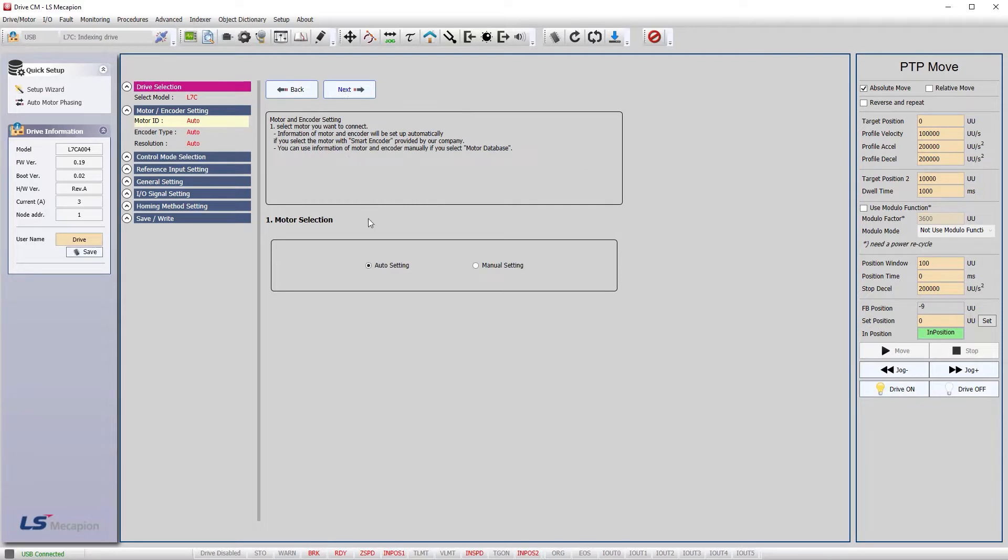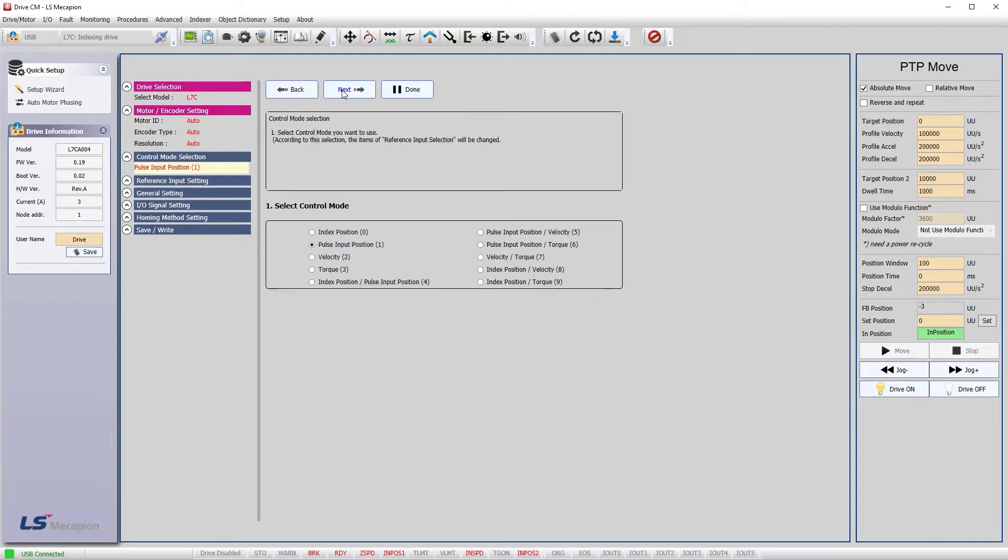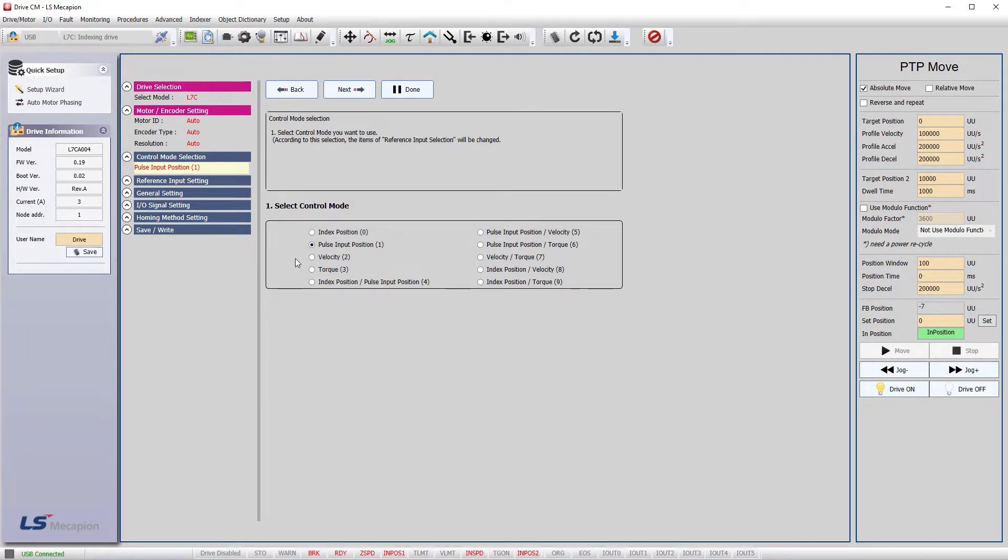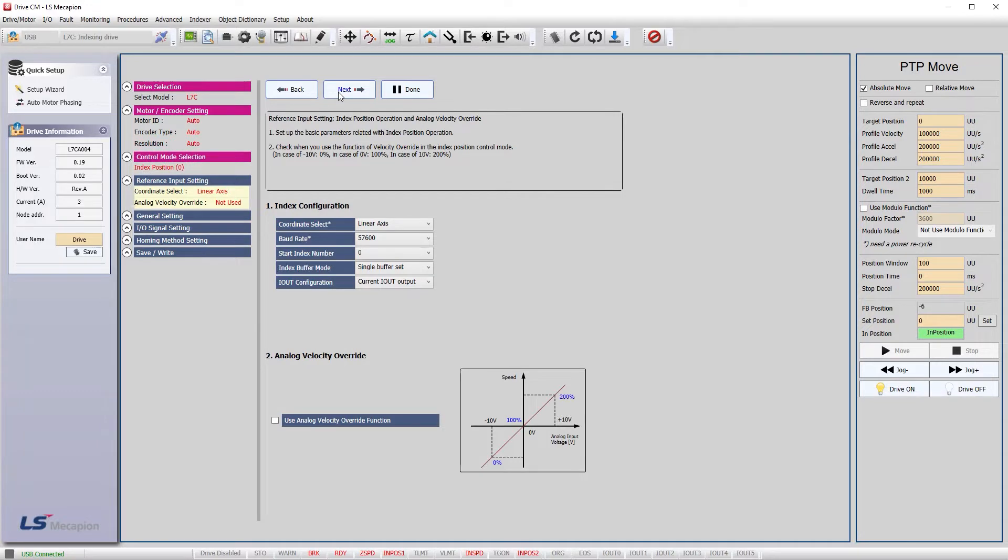We want to set up the encoder for auto and we want to be in Index mode. Homing doesn't make sense in Velocity or Torque modes and homing is handled by your controller in Pulse mode. You could use homing in the mode where you start in Index mode and then go to Pulse mode. This next screen is fine.